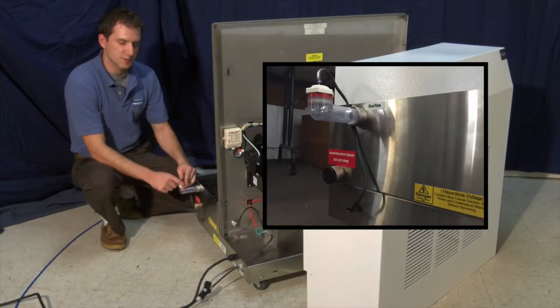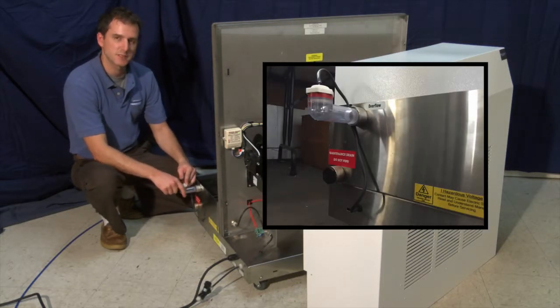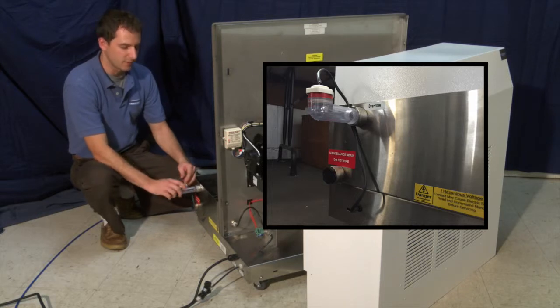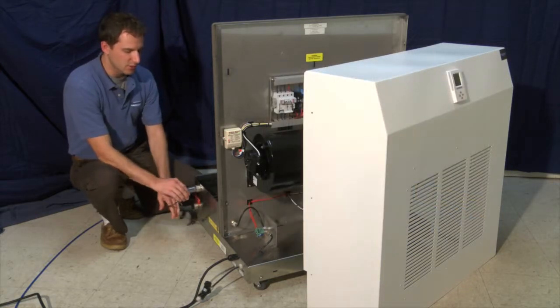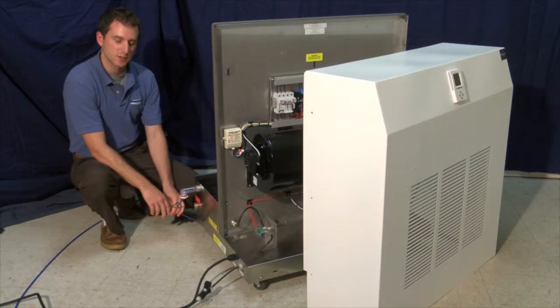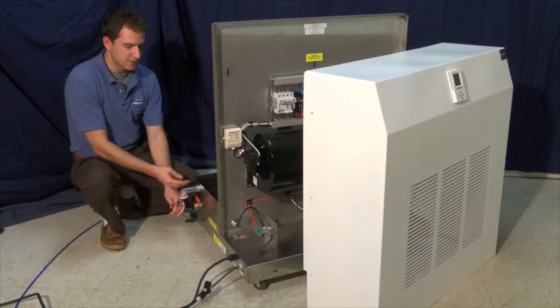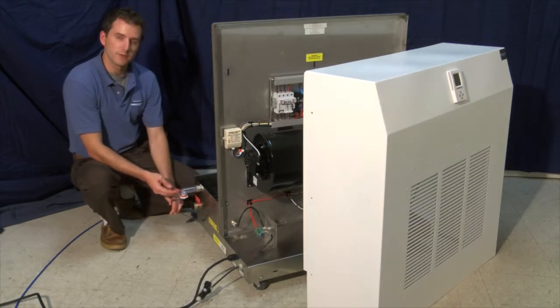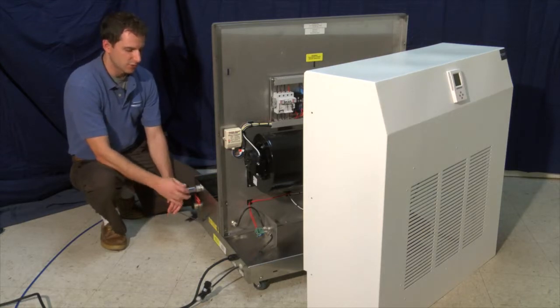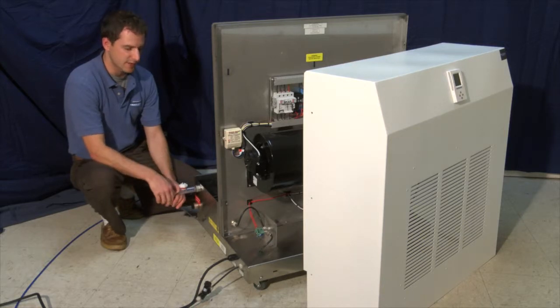Note, the prongs must be in the up position facing downward to work properly. If the tube is installed in the down position, condensation and water can pool on the sensor and give you false readings. Ensure the tube is in the up position with the prongs facing down.